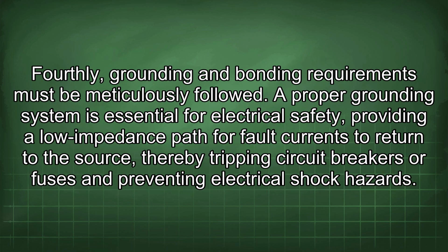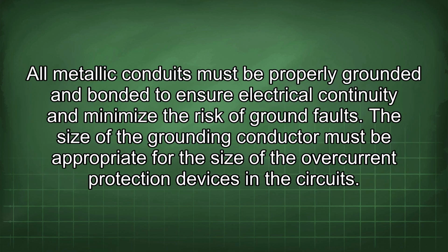Fourthly, grounding and bonding requirements must be meticulously followed. A proper grounding system is essential for electrical safety, providing a low impedance path for fault currents to return to the source, thereby tripping circuit breakers or fuses and preventing electrical shock hazards. All metallic conduits must be properly grounded and bonded to ensure electrical continuity and minimize the risk of ground faults. The size of the grounding conductor must be appropriate for the size of the overcurrent protection devices in the circuits.